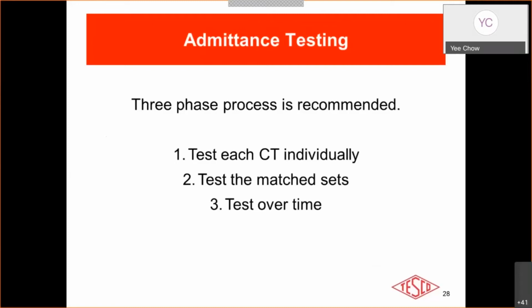Also, if you have a matched set of CTs, such as in a 9S meter installation where you have a bank of 3 CTs, if those CTs are of the same manufacturer, the same model number, same ratio, their admittance results should be the same. So, for instance, let's say you test a bank of 3 and you get values back of 12.6 and 12.8, and then suddenly 22.3 for phase C. Well, that can be an indicator that something is wrong on the C phase that would mandate additional troubleshooting. So like I said, the admittance testing results are not immediately intuitive. The results need a bit more analysis to know if you have good installation.